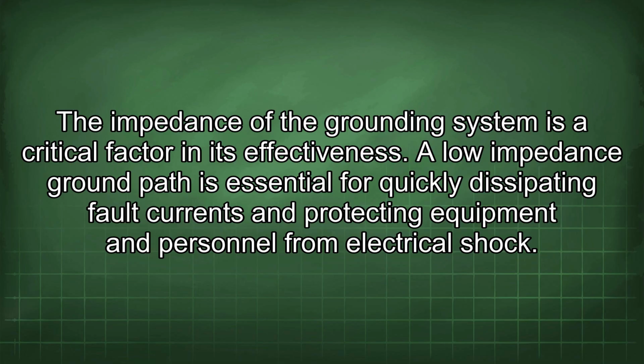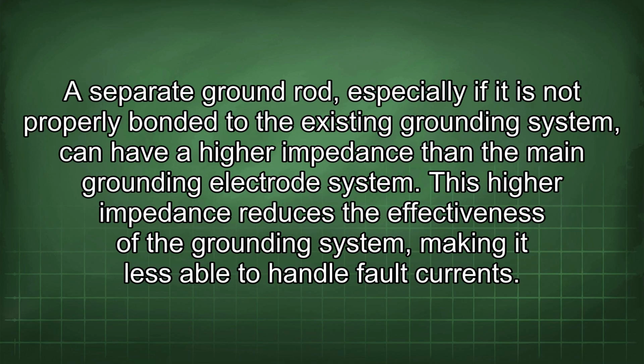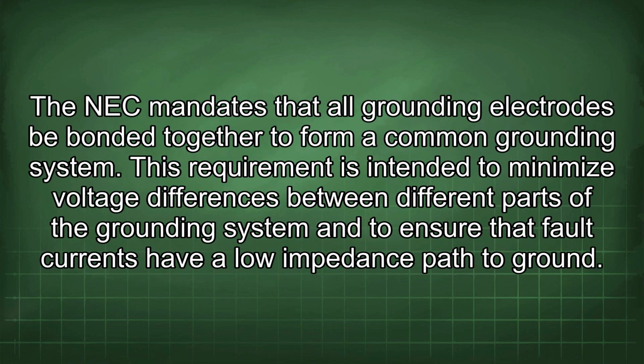The impedance of the grounding system is a critical factor in its effectiveness. A low impedance ground path is essential for quickly dissipating fault currents and protecting equipment and personnel from electrical shock. A separate ground rod, especially if it is not properly bonded to the existing grounding system, can have a higher impedance than the main grounding electrode system. This higher impedance reduces the effectiveness of the grounding system, making it less able to handle fault currents. The NEC mandates that all grounding electrodes be bonded together to form a common grounding system. This requirement is intended to minimize voltage differences between different parts of the grounding system and to ensure that fault currents have a lower impedance path to ground.